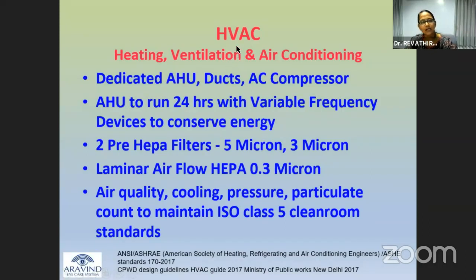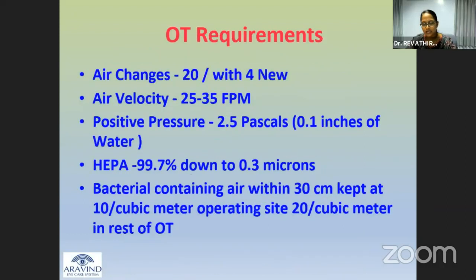So a dedicated heating, ventilation, air conditioning system has to function for an efficient OT. Dedicated air handling units, ducts, and AC compressors have to run 24 hours with variable frequencies. Two pre-HEPA filters, 5 micron and 3 micron, are preferable. With the laminar airflow, there is a dynamic change in the OT. So the air quality and cooling, pressure and particulate count should be maintained within ISO class 5 clean room standards. At least 20 to 30 air exchanges are required, with a minimum of 4 fresh air exchanges from outside. The measured air velocity and positive pressure have to be maintained inside the OT. HEPA filters definitely play an important role in modern OTs. They have revolutionized it, and there is no requirement for any fumigation process.